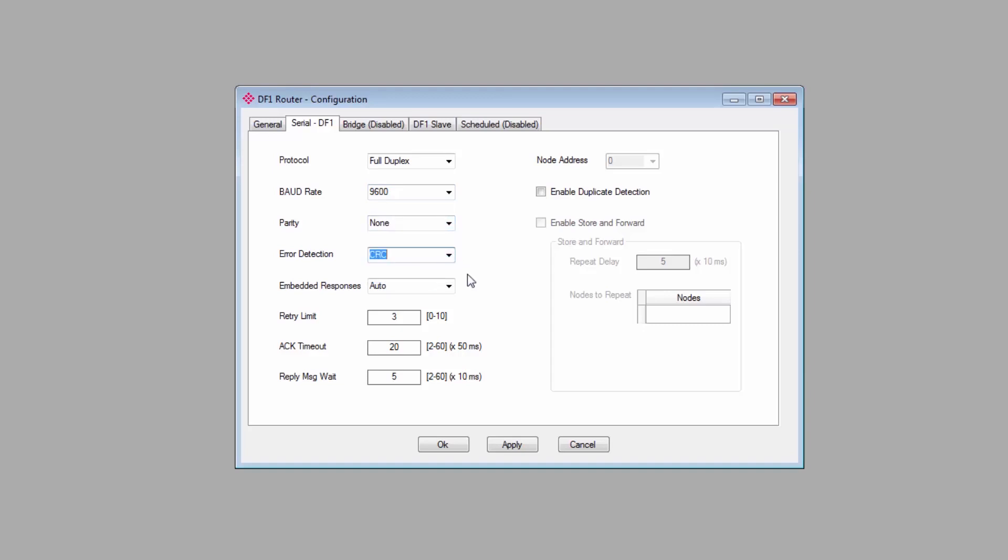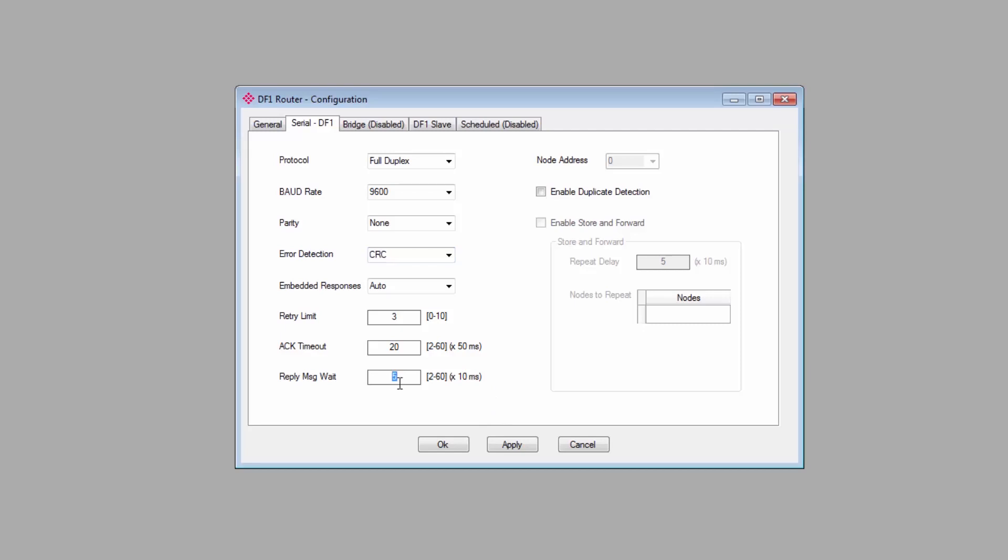Embedded responses, retry limits, and timeouts, just set to whatever you need. The reply message wait is intended for situations where some older legacy controllers, if the response comes back too quickly, they'll miss it. So you can add a slight delay to responses to ensure that the controller is able to process it. I'll just leave it at 50 milliseconds. There are a few other options available. Node address is relevant for certain modes where it's possible for the module to appear as more than one node. Enable store and forward is only relevant if you're using the DF1 radio modem protocol.